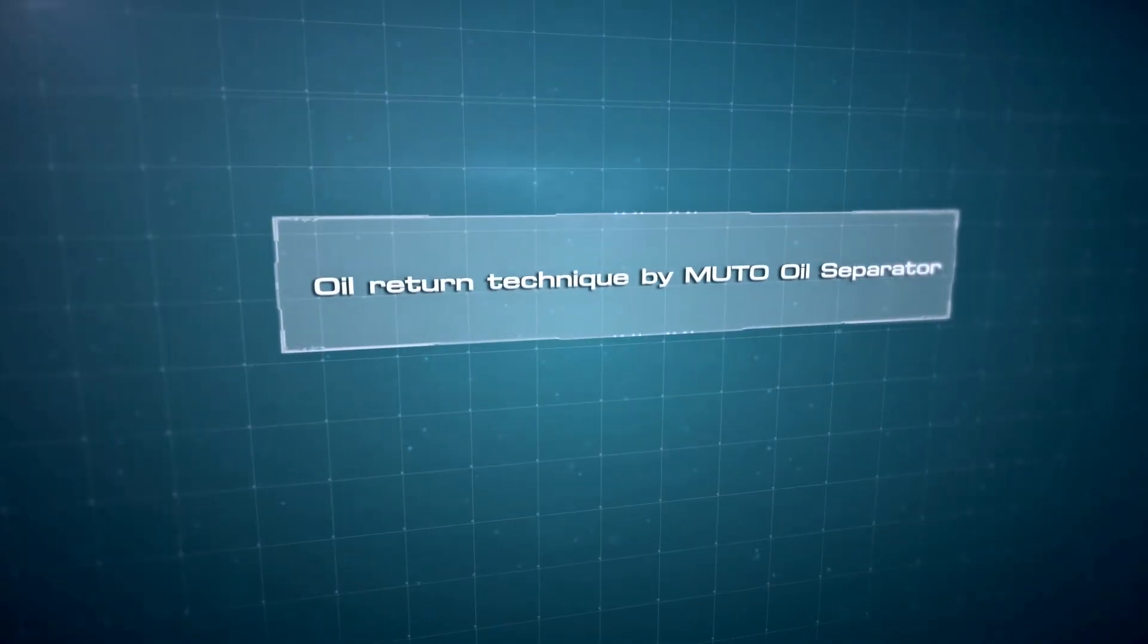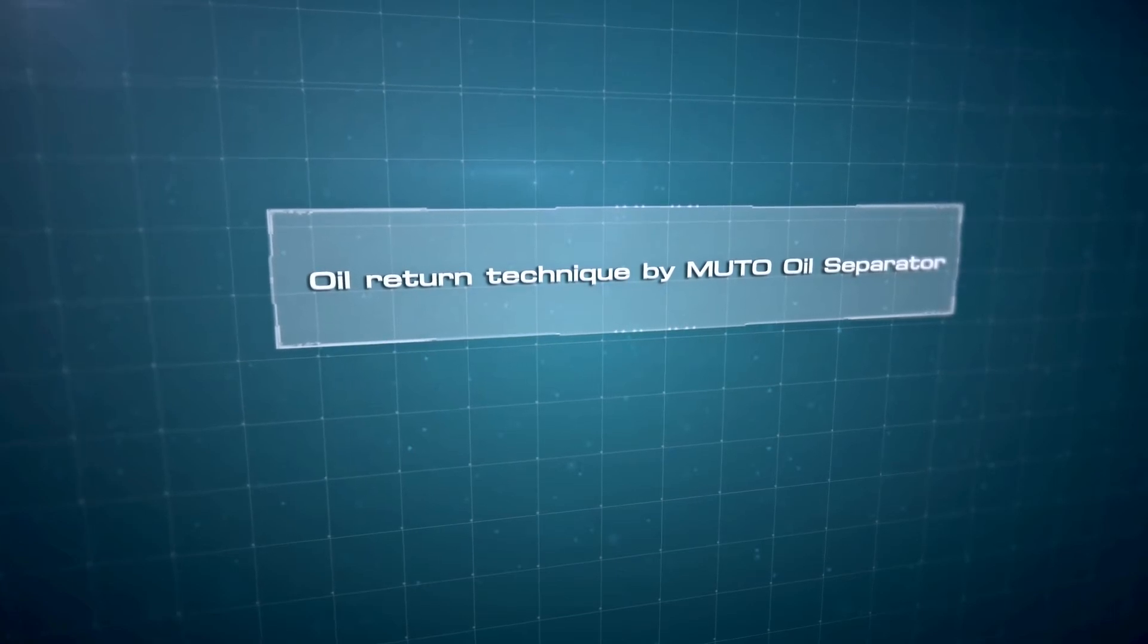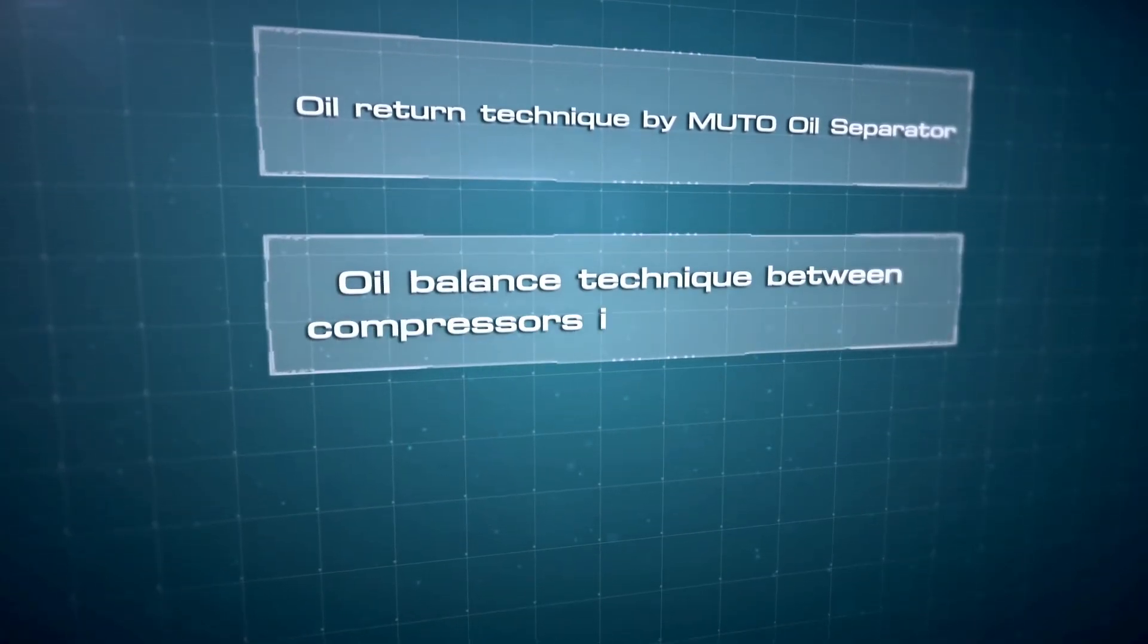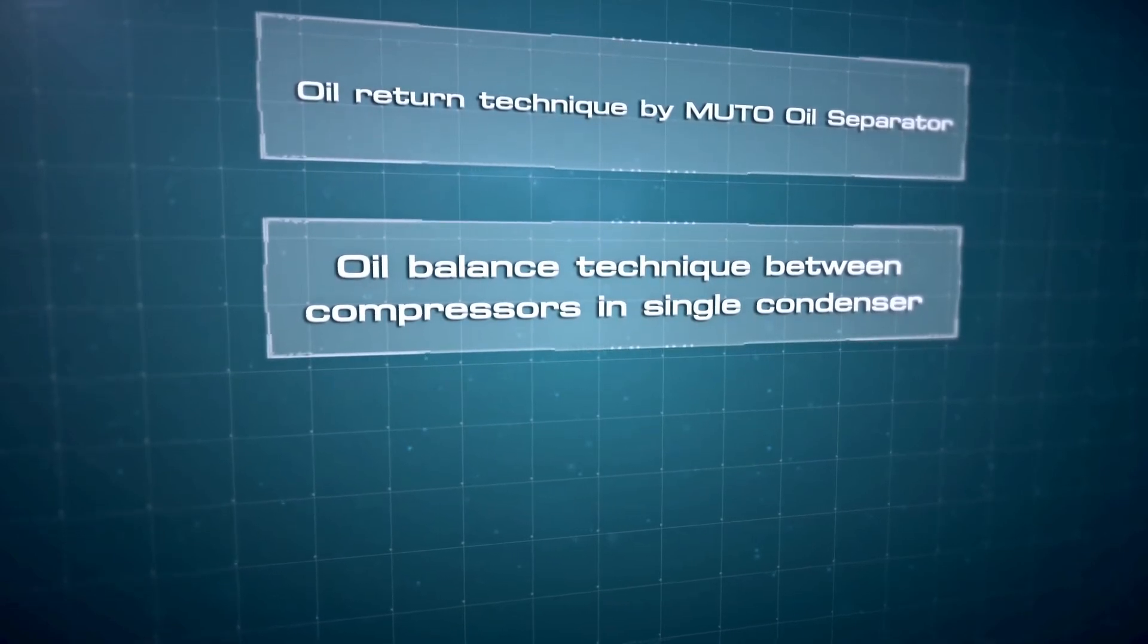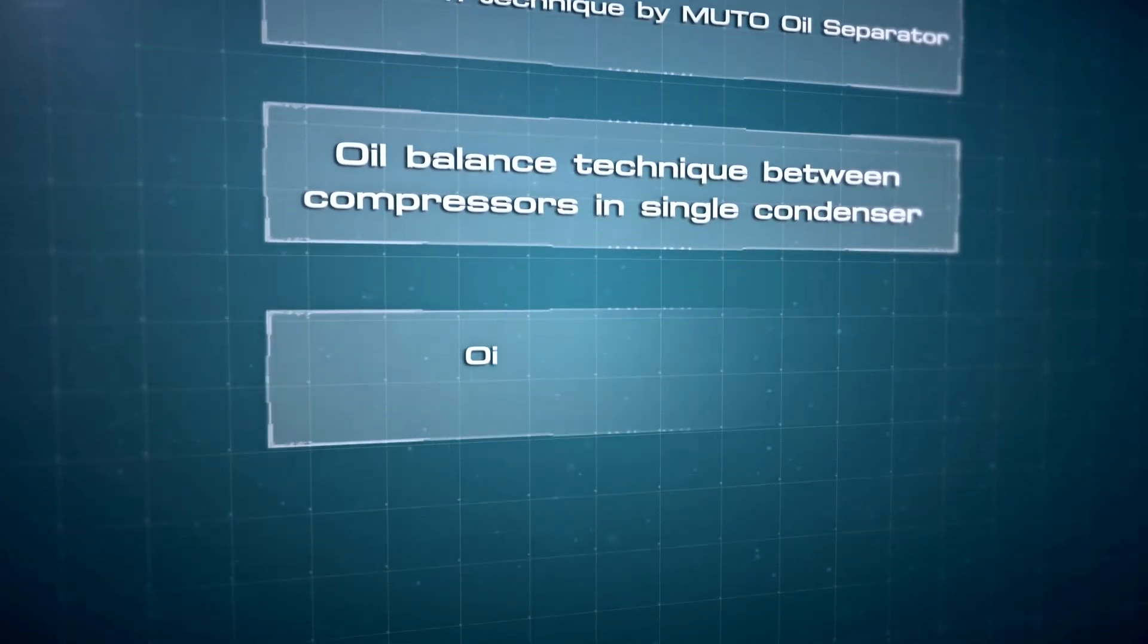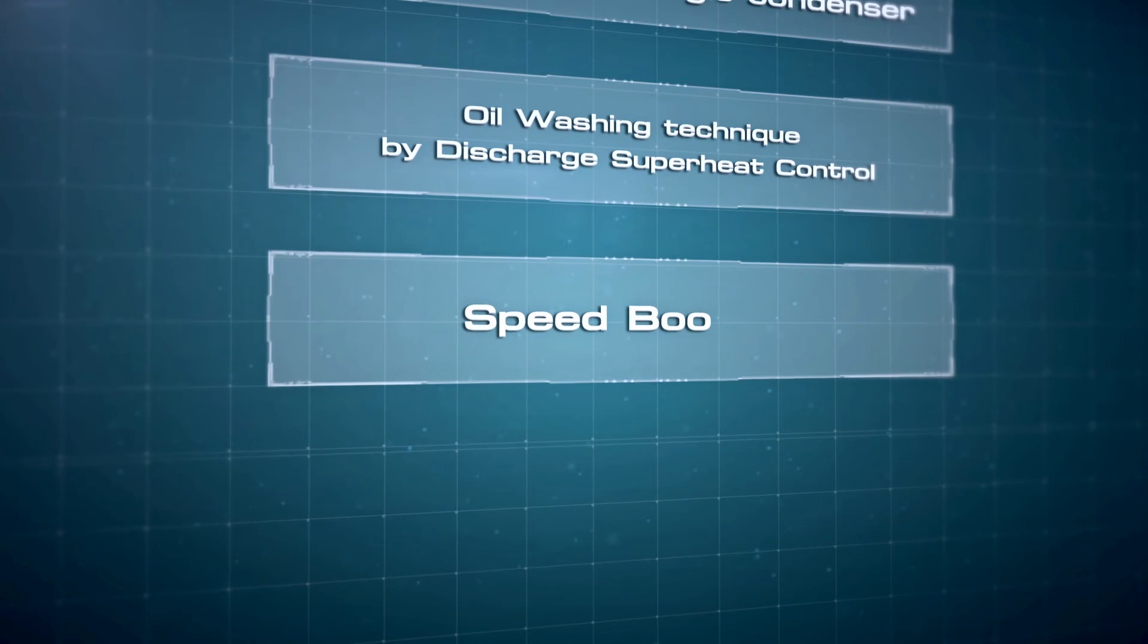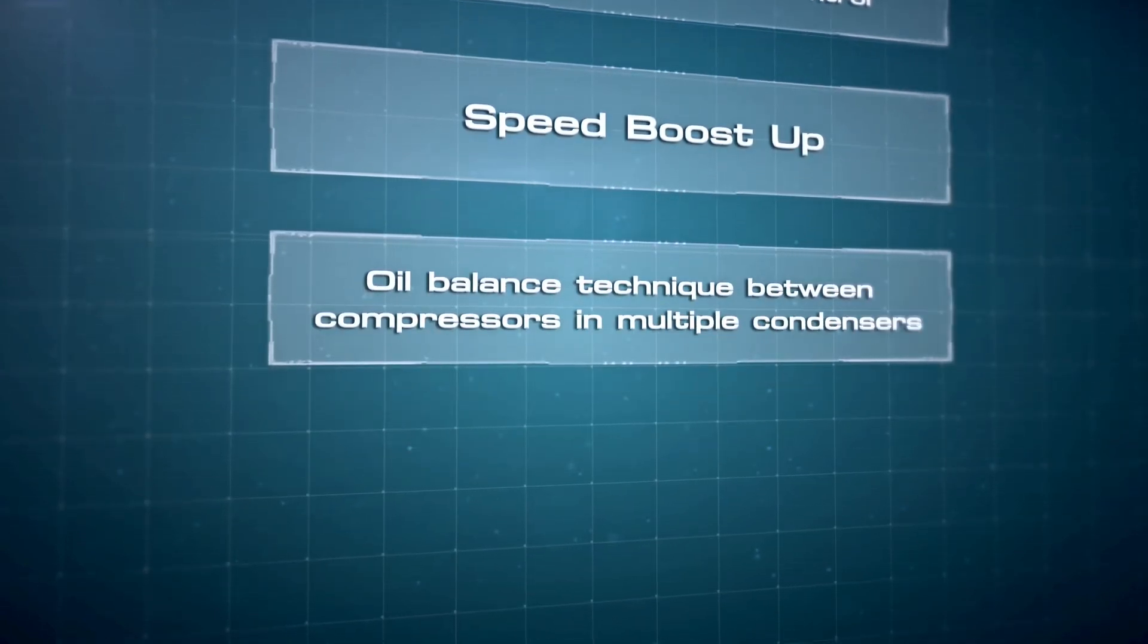The stages are: oil return technique by MUTO oil separator (please skip this stage in applications without oil separators), the oil balance technique between compressors in single condensers, the oil washing technique by discharge superheat control, the speed boost up technique, and the oil balance technique between compressors in multiple condensers.